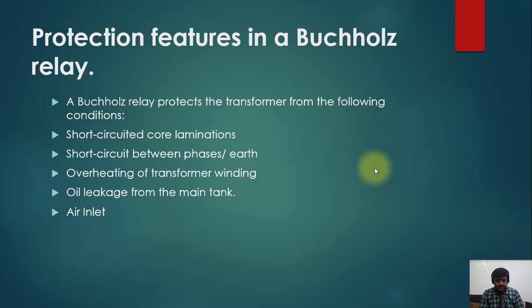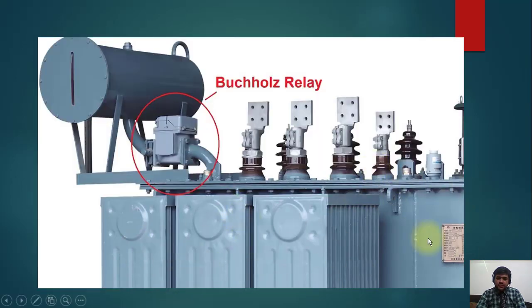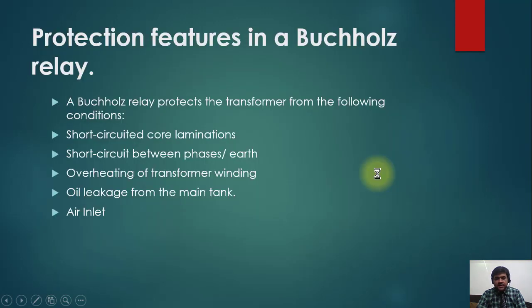The Buchholz relay operates on the following principle: whenever gases are produced inside the transformer, or air enters from an unknown external source, this air is trapped inside the Buchholz relay. Any fault in the transformer produces heat, which decomposes the oil and generates gas. This gas produces bubbles in the main tank. The bubbles rise naturally due to their low density, travel through the pipe, and get trapped in the relay — since the level of the Buchholz is slightly elevated.